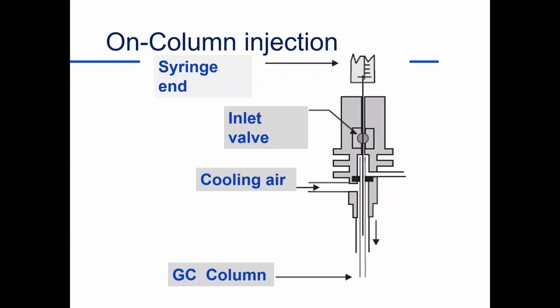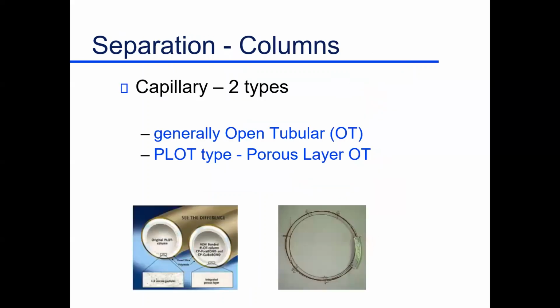So your first question, kind of always, is what kind of injection port do you use? What kind do you need? Is your sample heat sensitive? Do you have much material? Is it high concentration, low concentration? So a number of questions go into choosing your injection port. Probably 99% of the work is done with a split system. That's kind of the one that works. It's a really sensitive technique. It works well. So of the three that I showed you in detail, the split is by far most common.